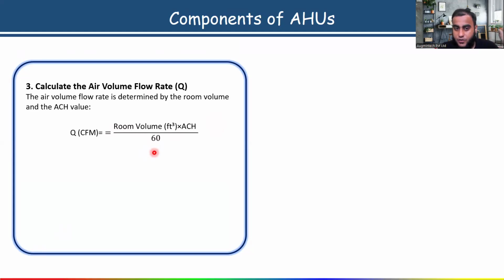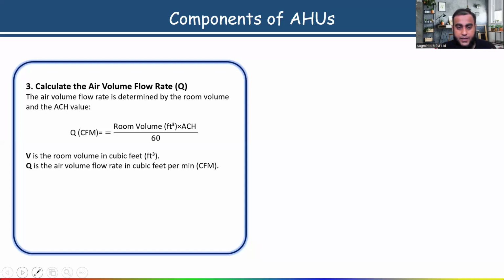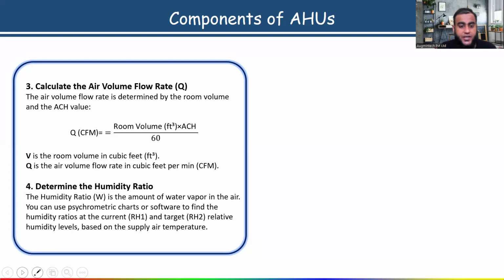So once you have calculated the room volume in cubic feet and the ACH value, you have done the selection of ACH value as per your building type. So by using this formula, or otherwise, if you know the airflow value already, if you have calculated, you can select that. Otherwise, this formula: room volume in cubic feet times ACH divided by 60. So you will get the airflow rate. Okay. Then you have to determine the humidity ratio value, means specific humidity. So how? Remember, the humidity ratio is the amount of water vapor in the air. So you can use the psychrometric chart, or we have software also. I will explain, okay, by using the software to find out the humidity ratio at the current relative humidity.